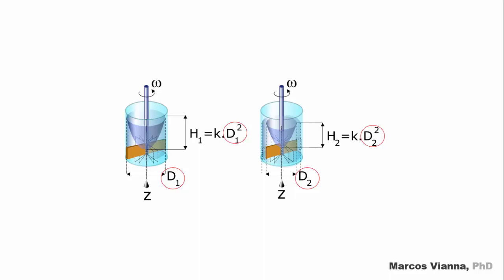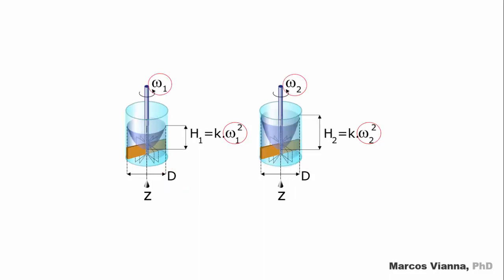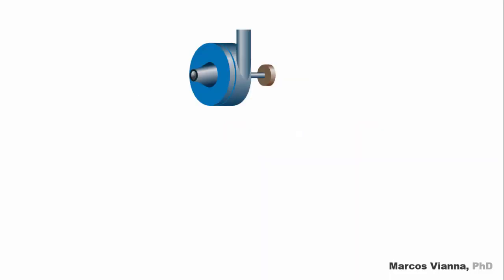We can now make two observations that will be important in the study of pumps. The first is that the height that the water can go up inside the cylinder will depend on the impeller diameter. The height will vary with the square of the diameter. Also, it will vary with the square of the impeller rotation velocity.